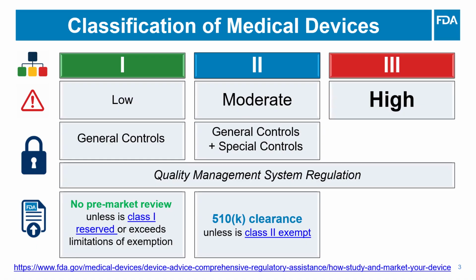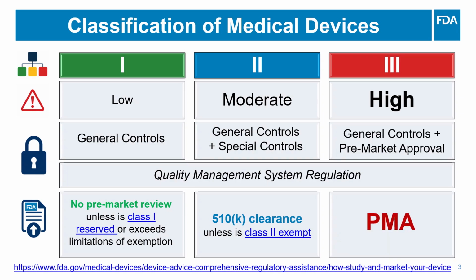The FDA classifies into Class 3 devices intended to be used in supporting or sustaining human life, or that present a potential for unreasonable risk of illness or injury. Most Class 3 devices require pre-market approval, or PMA. This is the most stringent regulatory pathway and includes, for example, review of manufacturing information. Before FDA approves a PMA, the sponsor must provide valid scientific evidence demonstrating reasonable assurance of safety and effectiveness for the device's intended use. Devices that didn't exist or were not known before the date of the Medical Device Amendments of 1976 and have not been classified by FDA are automatically classified into Class 3 regardless of the level of risk for that product.